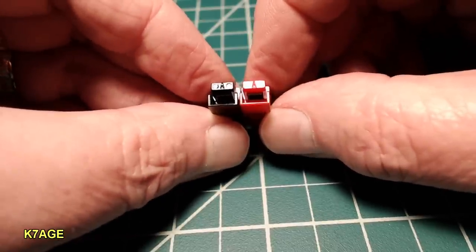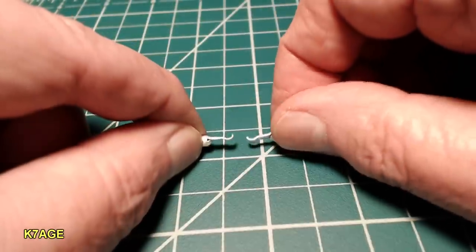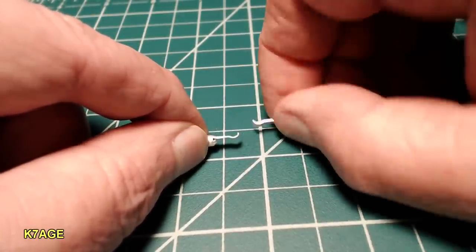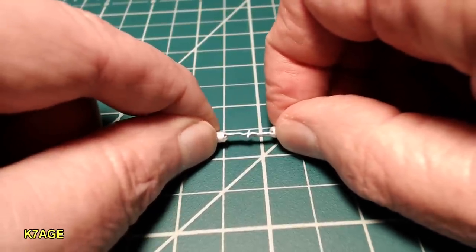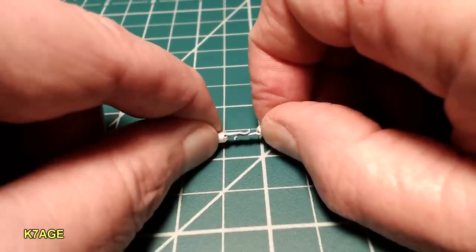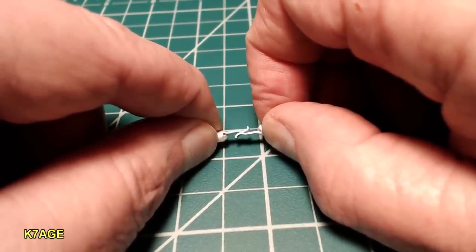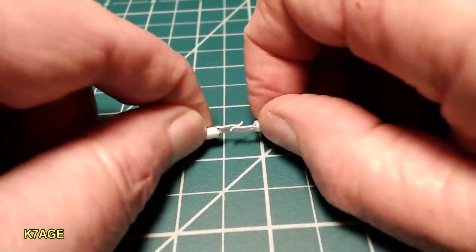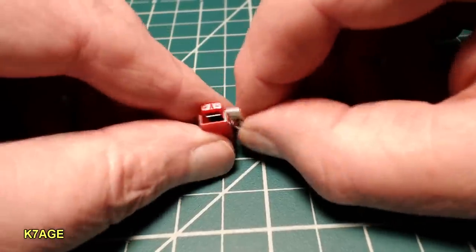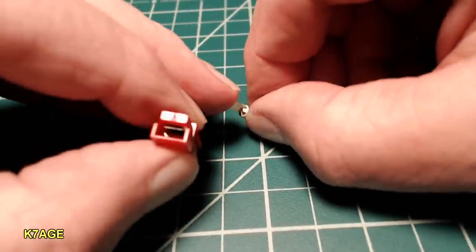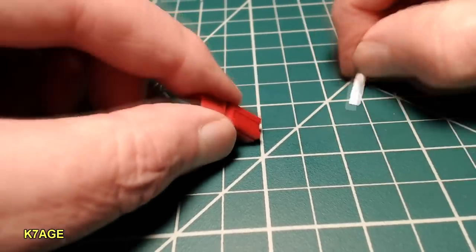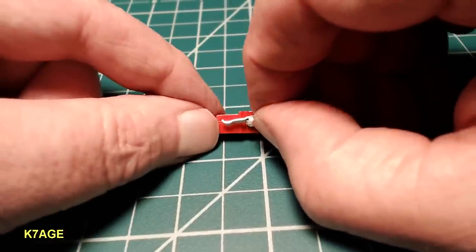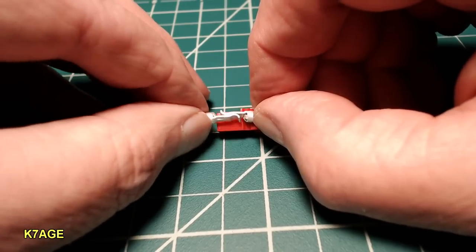Again, read A, red on right, be able to read the A. Okay, here's a couple of the pins. And when they mate together, they're flipped around opposite each other. And so it pushes together and goes, bumps past the tongue there. And that's the mating section for the connector. And again, you can mate a 15 or 30 or 45 amp connector together because the pin, the contact area is the same. It's basically the diameter for the wire size. So the connector pin will be inside the body in this orientation with the tongue, the curved side facing down. And look at it from the side view. It'll be like this. It'll be inside like that. And, of course, the other one will plug in from this side and mate.